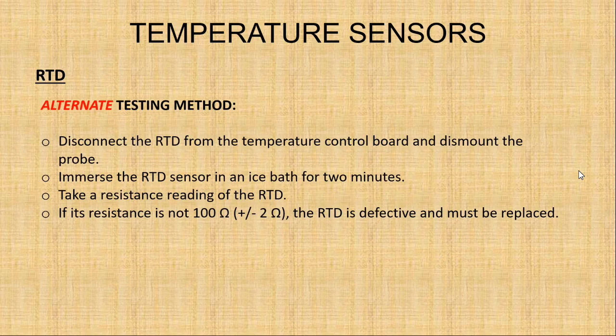An alternate method that you can use is, again, knowing what type of probe it is. In this case, we're going to talk about that PT100. You can disconnect the RTD from the temperature control board and dismount the probe. Take the tip of the probe and immerse it into an ice bath for 2 minutes. Take a resistance reading of the RTD. If its resistance is not 100 ohms, the RTD is defective and must be replaced.